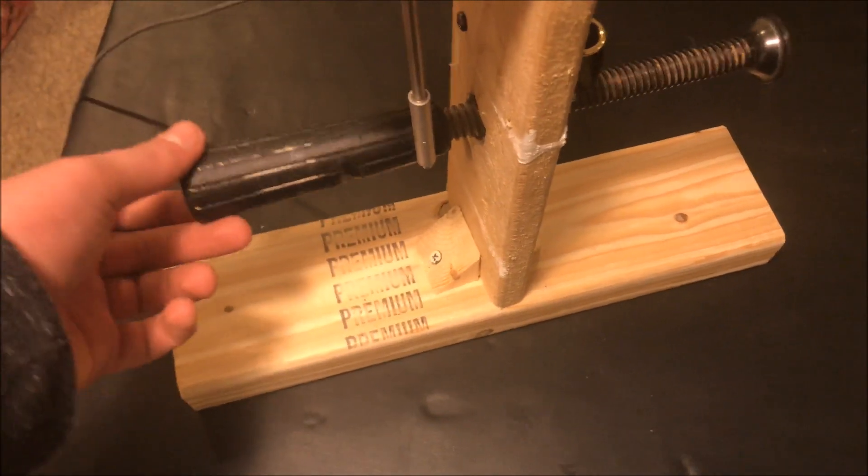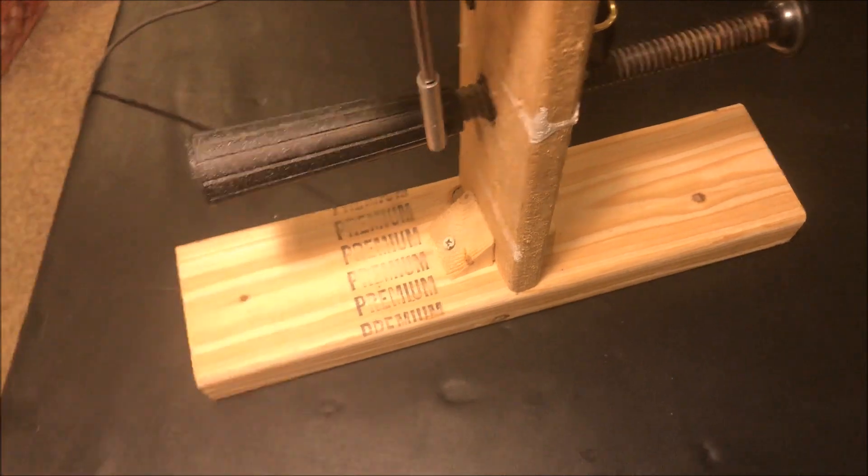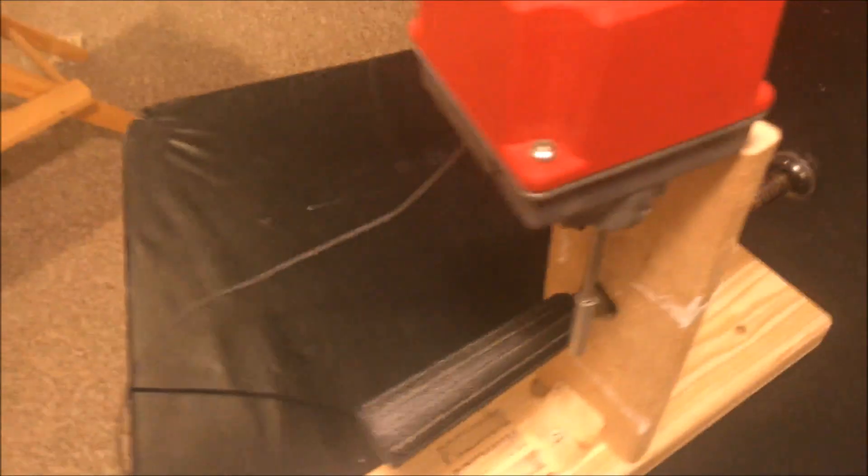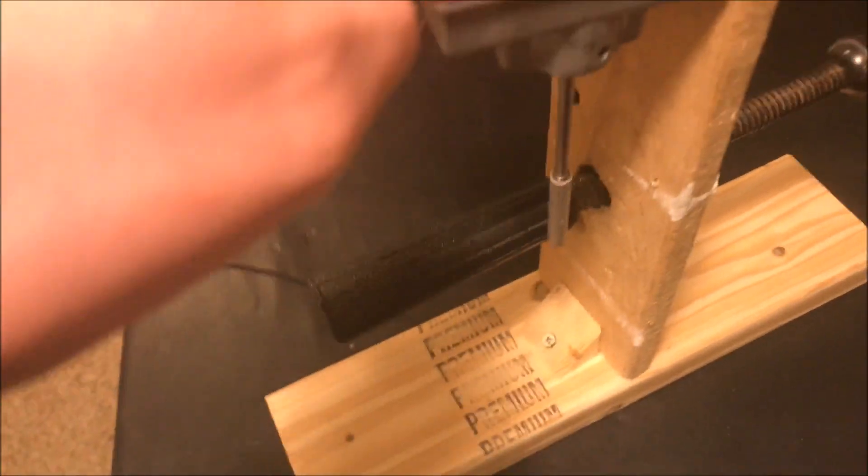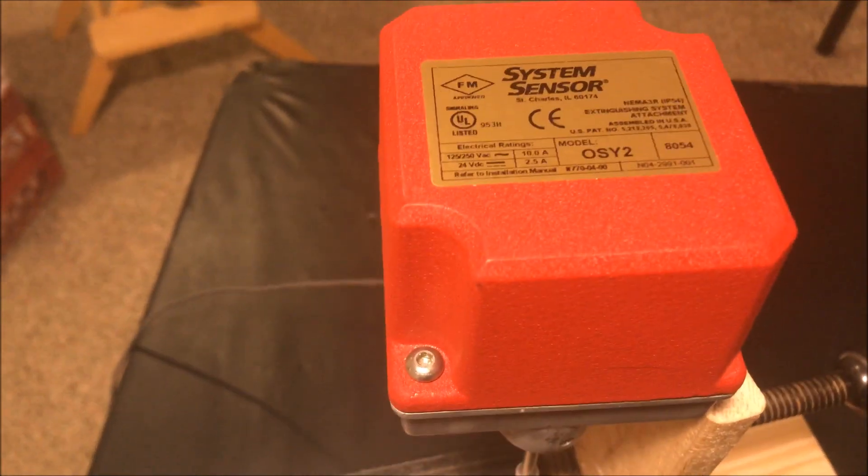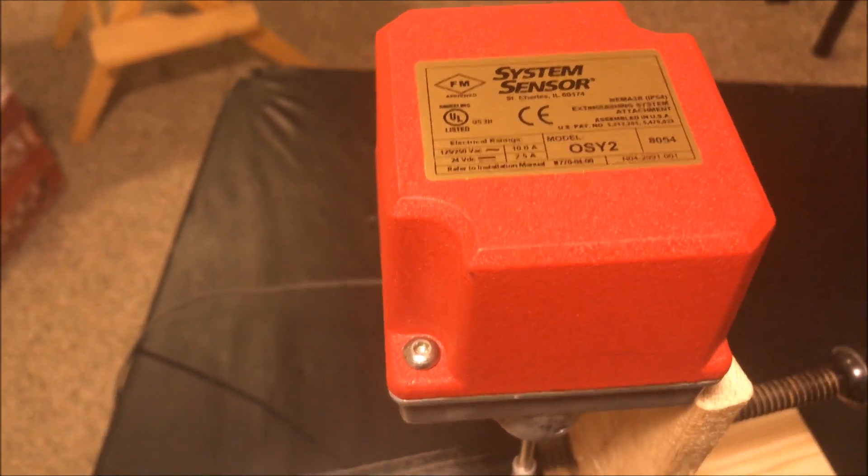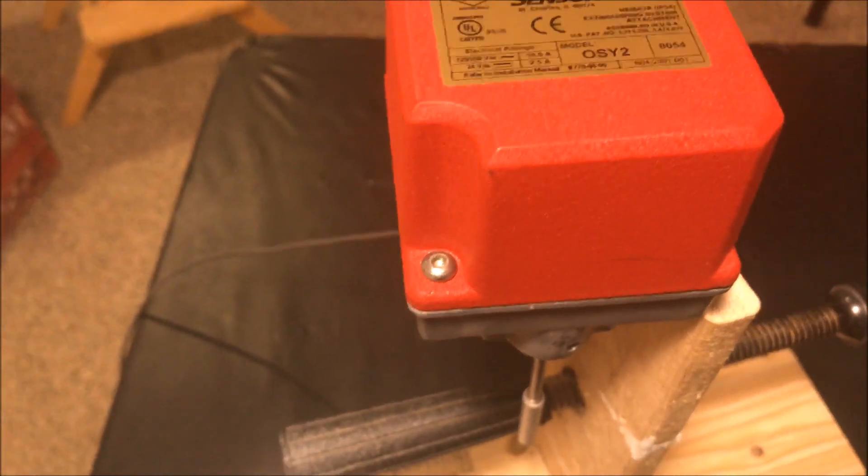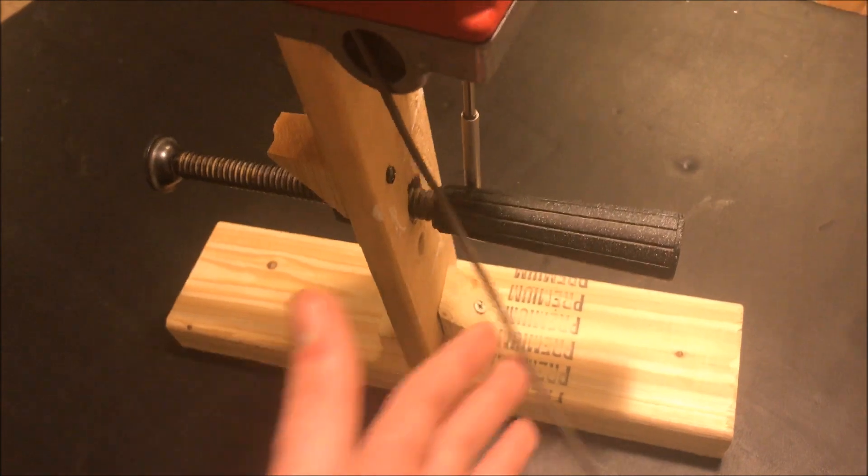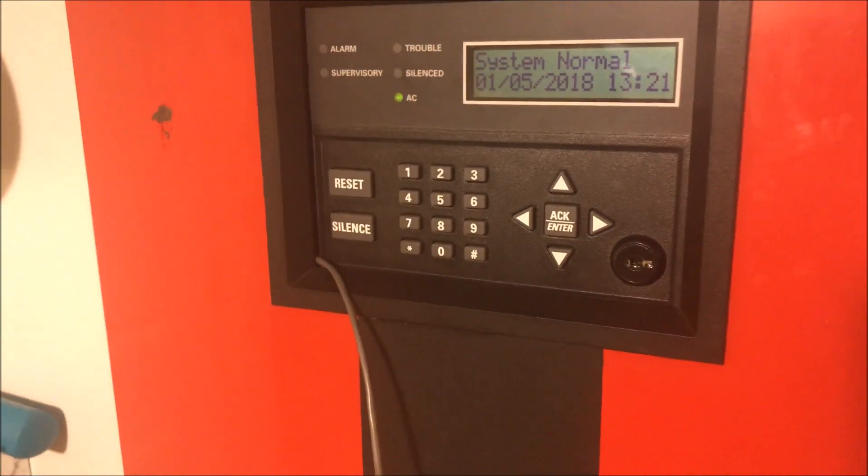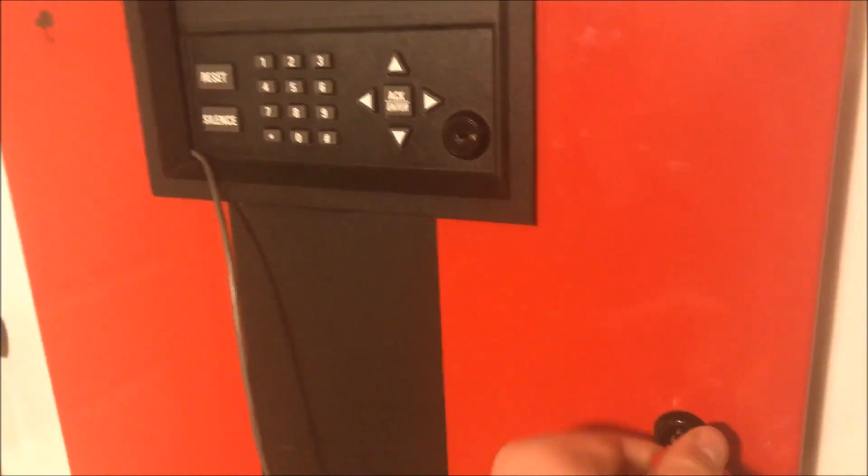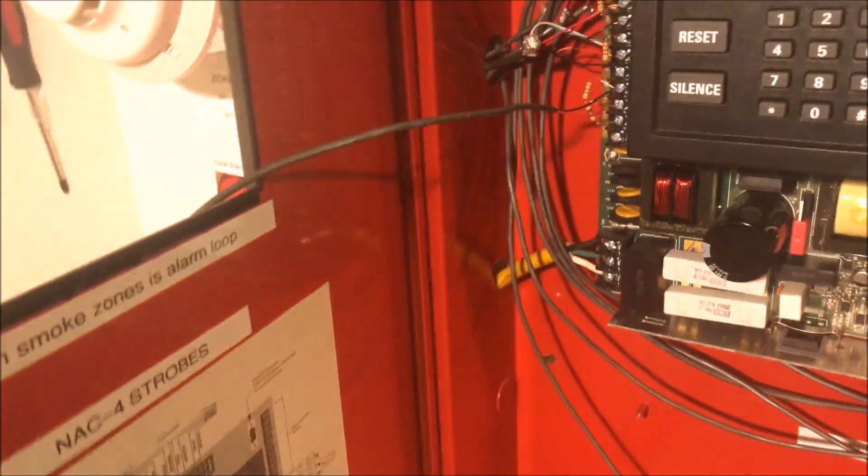So right now the valve is sitting in what would be its closed condition. Up top here, what would be like on the pipe is a System Sensor OSY2 supervisory switch. The way that this works is coming out of it, there's a wire, normally being conduit way nicer than the way I have it and that's going to go up into my panel. Again, this is nowhere near compliant of anything. This is just for demonstration purposes only.